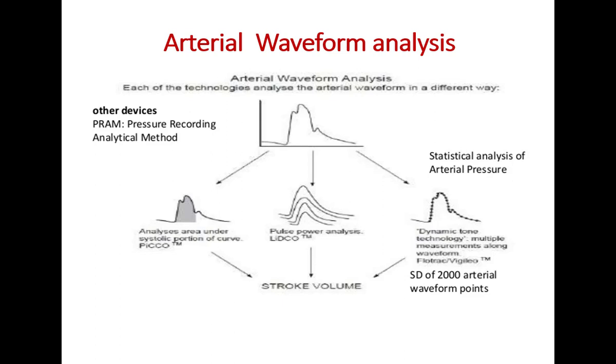The LiDCO uses what's called the pulse power analysis, and your Vigileo FloTrac monitor, the FloTrac and the Vigileo, uses what's called the dynamic tone technology. What it does is that it measures the same waveform almost 100 times over a 20-second period, and then it reconstructs and puts it into an algorithm and tells you that this is the stroke volume.